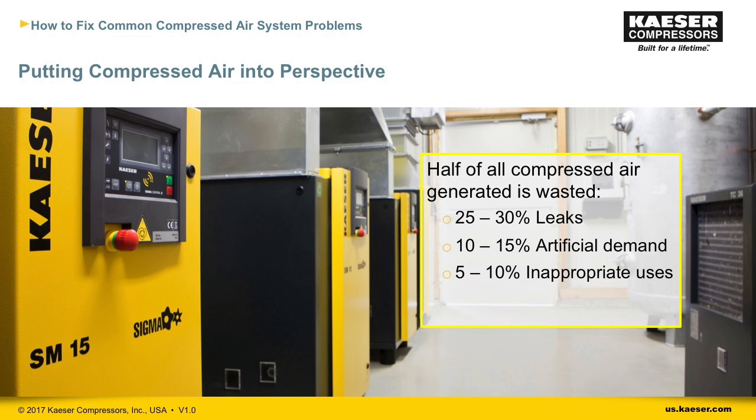Additionally, based on countless compressed air system audits, the DOE estimates that half of all compressed air generated is wasted. The components of that waste are leaks, artificial demand, which is operating at a higher pressure than necessary, and inappropriate uses. If you think about compressed air as an input to production, 50% is a very poor yield.